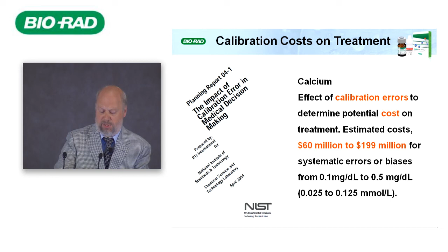Major service of the instrument requires calibration, and for sure when recommended by the manufacturer. The calibration cost on the treatment: here I have an example from the States on calcium. If you don't do a proper calibration on calcium, this error costs about $60 to $199 million annually because of additional investigation of the patient and maybe wrong or misleading treatment. Calibration verification means the assaying of material of known concentration in the same manner as patient specimens to substantiate the instrument or test system's calibrations throughout the reportable range for patient test results. And this is representing the quality control.